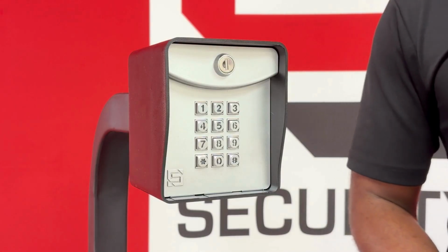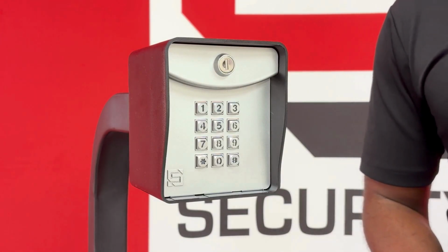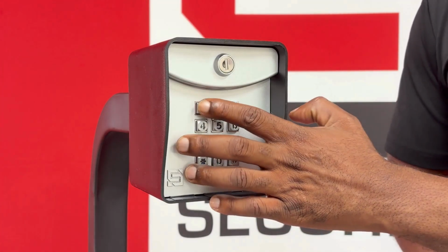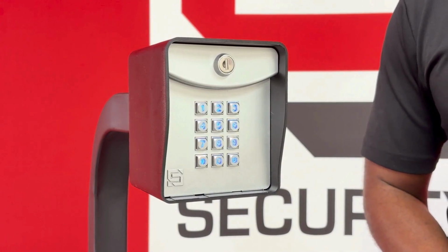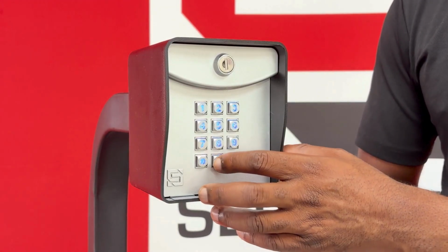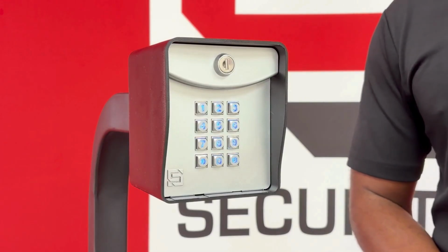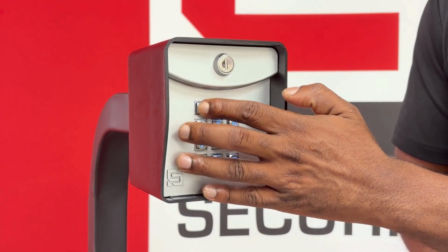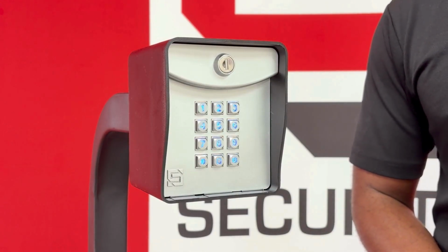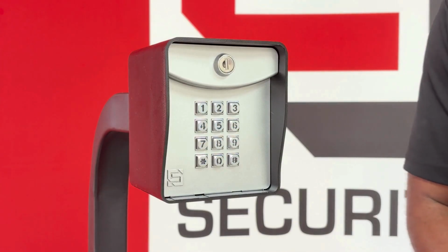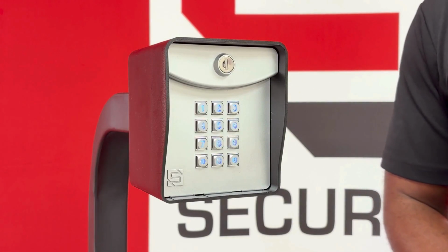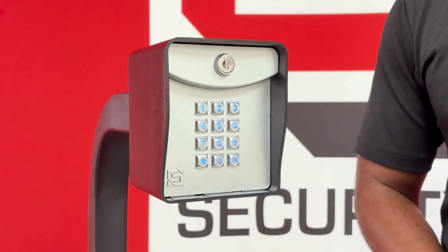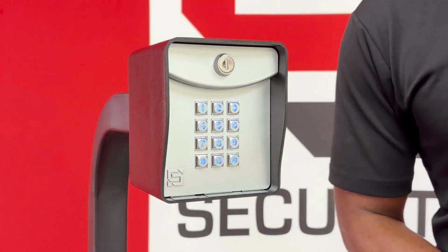Next on our Ridge keypad, we're going to show you how to delete all the codes out of the keypad. Again, we're going to be using our default master code, which is 1251. Then we're going to enter submode 0. After entering submode 0, we'll enter the master code again to start the deletion. You'll hear the keypad beep as it deletes all the codes, and you'll get a positive confirmation once complete. There we go. We'll go ahead and hit pound to exit programming mode, and now all codes are deleted.